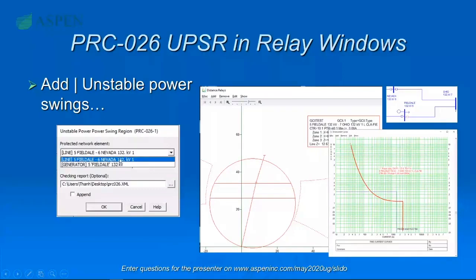First, as a disclaimer: we are tool makers. We read the PRC ourselves and tried to understand it, but that's our interpretation. Always read the PRC text and interpret it yourself — if you agree with us, go ahead and use the Aspen tool; if not, make the decision on your own. Key findings: first, when you run PRC-26, there has to be a network reduction done — if your network model is not up to date or has anomalies, you won't get a good result. Second, because you need to correctly identify the remote end of the line to build the sending and receiving end equivalent model, you need to pay attention to TAP lines and three-terminal transmission lines.